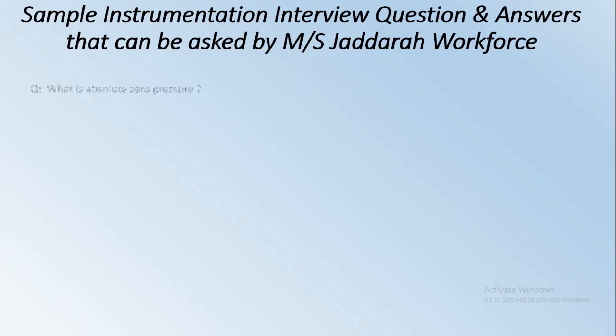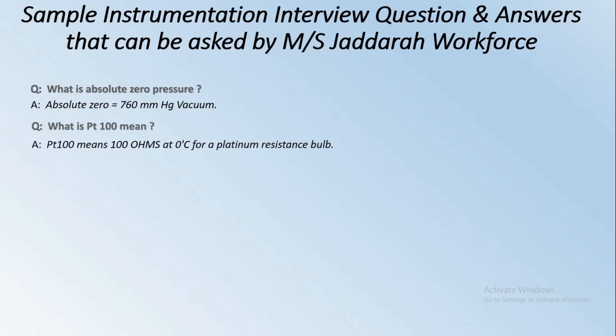First question: What is absolute zero pressure? Absolute zero equals 760 mm of Hg vacuum. Next: What is PT100? PT100 means 100 ohms at zero degrees centigrade for a platinum resistance bulb.